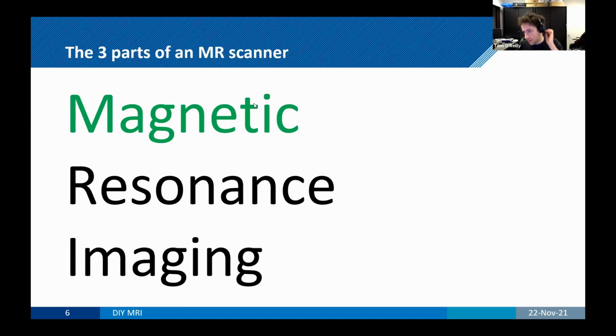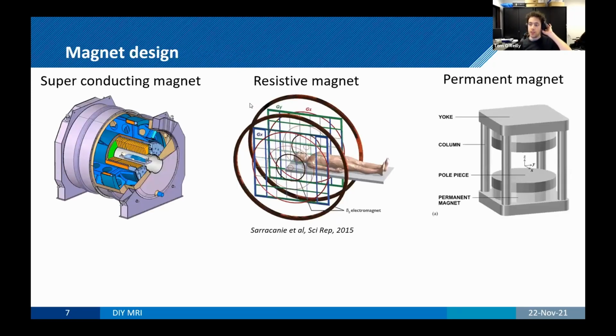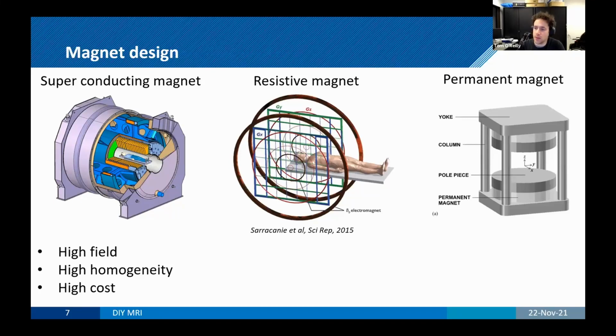So start off with the magnet. There's generally 3 categories these fall into: the superconducting systems, the resistive systems, and the permanent magnet systems. The superconducting systems are typically made by specialist companies with a lot of experience, because it's a very complex thing to do, working with superconducting wires and making sure all the forces are properly balanced. It's very hard, but these vendors are able to produce magnets.